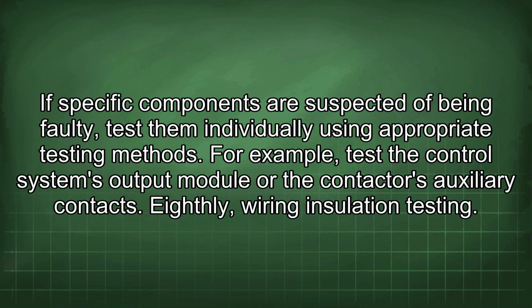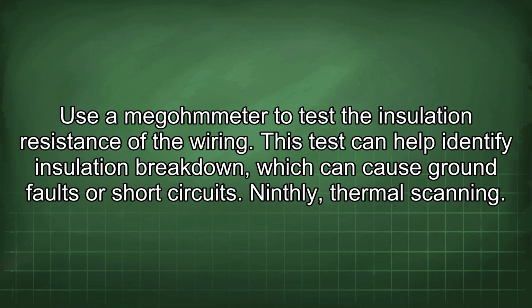Eighthly, wiring insulation testing. Use a megohmmeter to test the insulation resistance of the wiring. This test can help identify insulation breakdown, which can cause ground faults or short circuits.